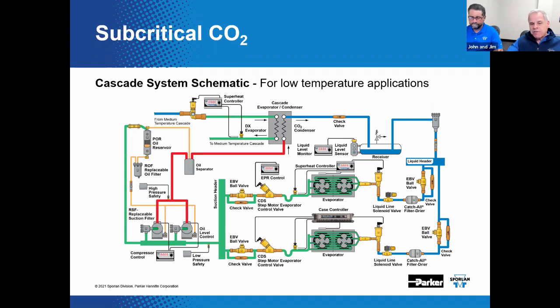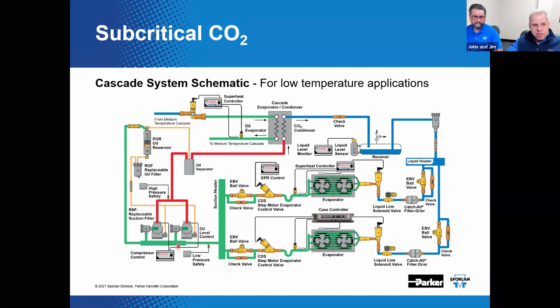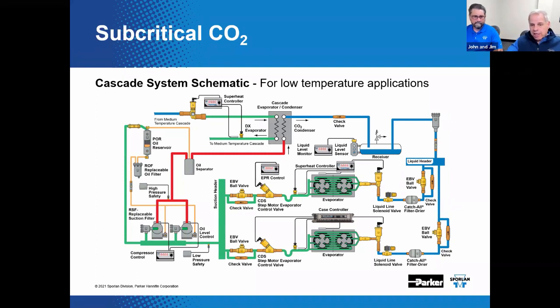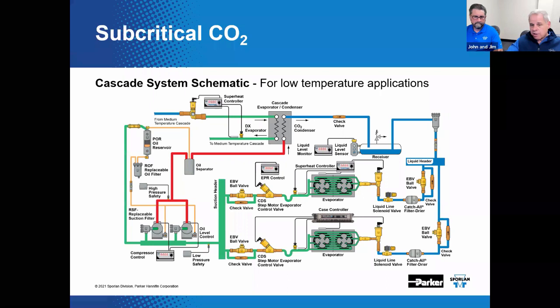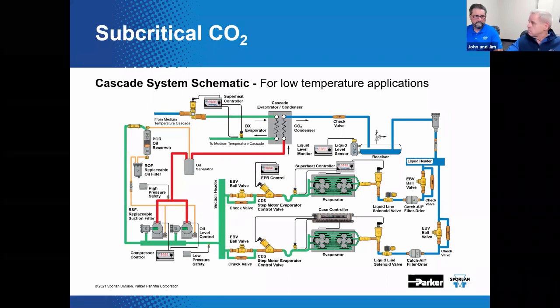Once the CO2 leaves the evaporator, it is compressed by a bank of compressors on the bottom left of the schematic. You see them right here, which reject heat to the heat exchanger that is cooled by the DX high side system. Look at this as a normal DX system, but instead of having a traditional condenser, it has an intermediate plate heat exchanger referred to as a cascade evaporator condenser, which you see here on the schematic.